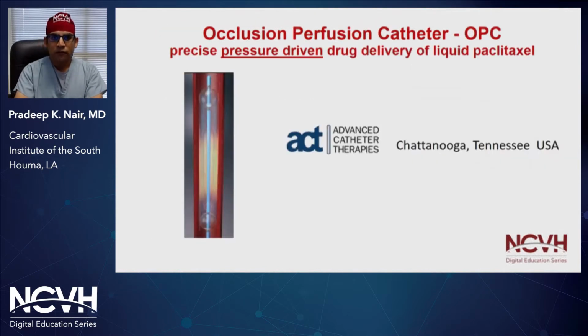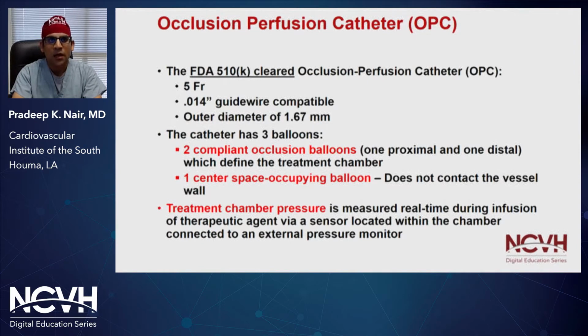So this brings us to the concept of localized drug delivery of paclitaxel, and in this case, we utilize the Occlusion Perfusion Catheter, which utilizes pressure-driven drug delivery of liquid paclitaxel. The OPC catheter is an FDA 510(k) cleared device that is 5 French and 0.014 inch guide wire compatible. It has an outer diameter of 1.67 millimeters, and there are 3 balloons associated with this catheter. There are 2 compliant occlusion balloons, one proximal and one distal, that define the treatment chamber. There is 1 center space-occupying balloon that never contacts the vessel wall, but assists in distribution of the drug. And there is a treatment chamber pressure that is measured in real time to monitor the internal pressure for drug delivery.